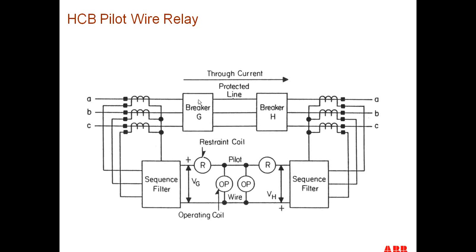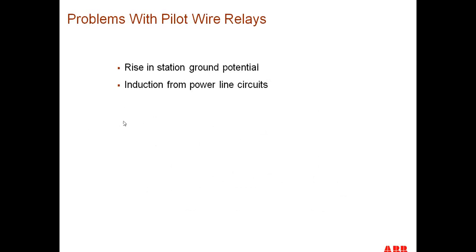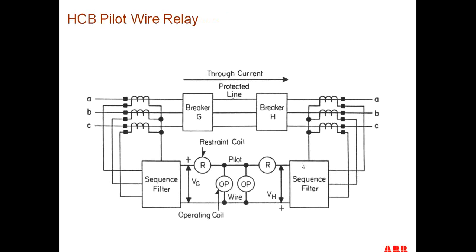Here we had a protected line as we had before, as in modern days. We have current transformers at both ends of a line. But now the current transformers would feed into a sequence filter, and a sequence filter, if you remember, would make the relay responsive to positive, negative, and zero sequence current, and it actually had taps on the relay for matching to positive, negative, and zero sequence current. And the output of the sequence filter was a sequence voltage. And the sequence voltage was then impressed on the pilot wire.